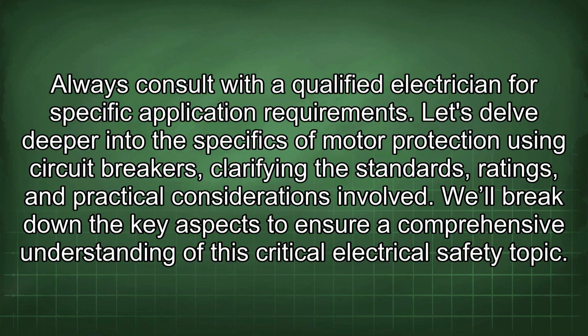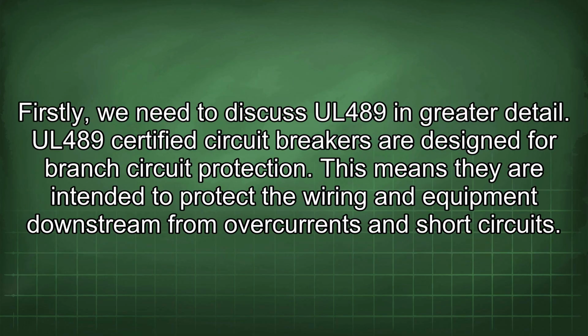Let's delve deeper into the specifics of motor protection using circuit breakers, clarifying the standards, ratings, and practical considerations involved. We'll break down the key aspects to ensure a comprehensive understanding of this critical electrical safety topic. Firstly, we need to discuss UL 489 in greater detail. UL 489 certified circuit breakers are designed for branch circuit protection. This means they are intended to protect the wiring and equipment downstream from overcurrents and short circuits.